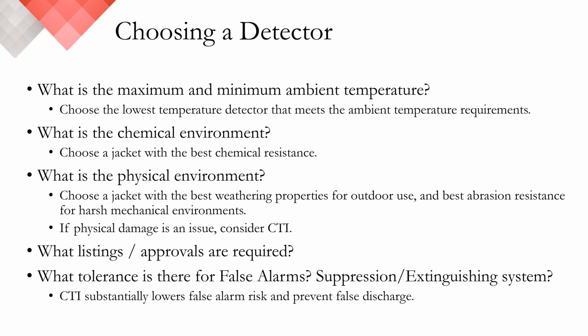When choosing a detector, the first step is to choose the lowest alarm temperature rating which has an ambient temperature appropriate for the application. Then, choose a jacket type most suitable for the environment. Consider both physical and chemical conditions it will be exposed to. It's also important to consider what listings or approvals may be required. Not all detectors have both FM and UL ratings. And lastly, CTI should be considered for all applications where false alarm discrimination is crucial.